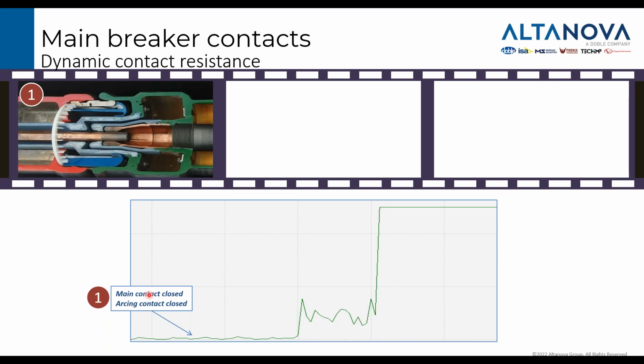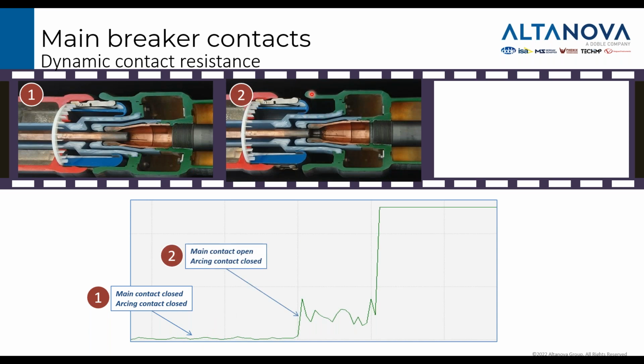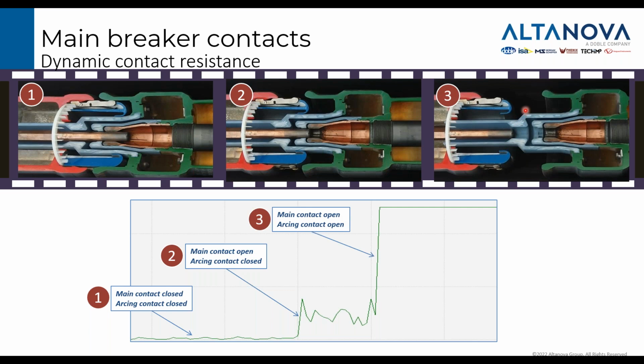This is a real measurement. So we start from the moment the circuit breaker is closed. So the main contact, this is the main contact, and this is the arcing contact. So the circuit breaker is closed, and in the graph the value is very, very low. At this moment the main contact is open, but the arcing contact is still closed. So we start to see an increase of the resistance value that will stay for a few milliseconds, and then the arcing contact, so the circuit breaker, is totally open. So the value of the resistance in the graph goes to a high value.